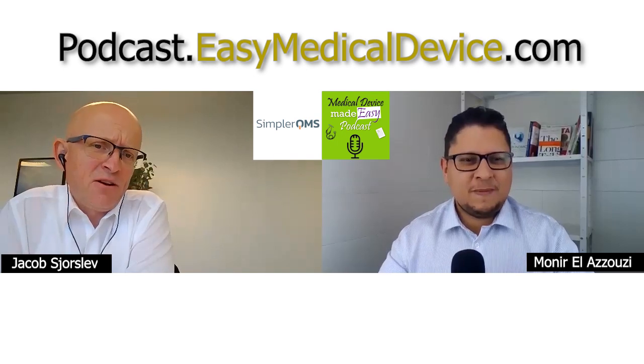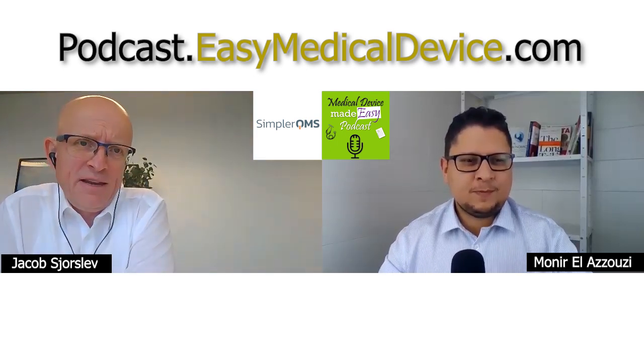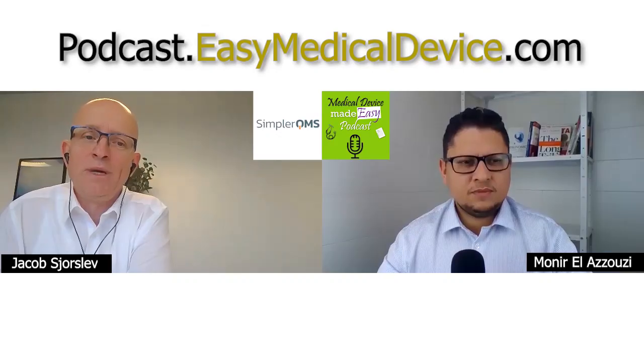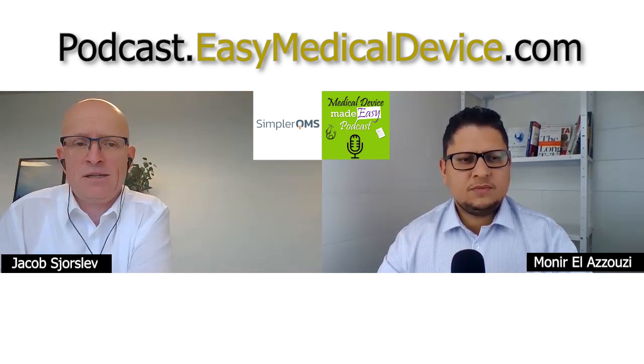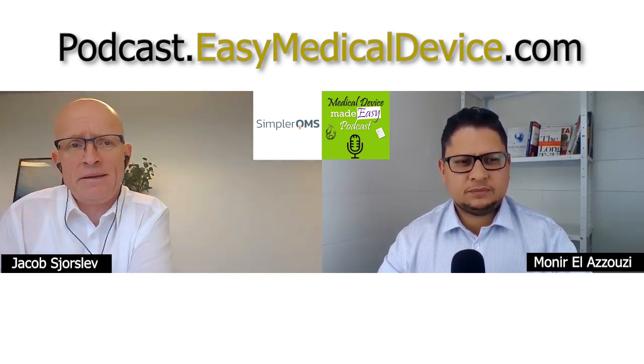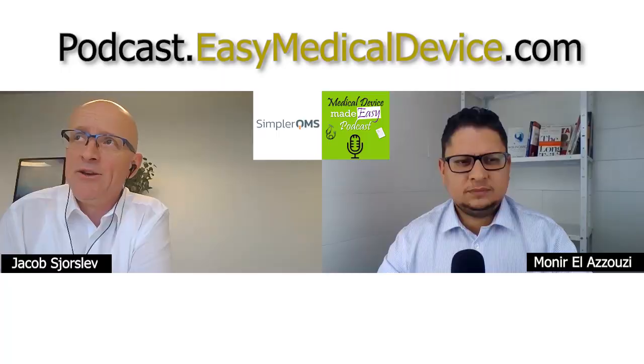And I think I should also make a point that if you have implemented a standard system in a standard way, that's easier to validate, instead of if you started with a standard system and then you did a lot of custom coding. All those custom codings, you have to validate individually and prove that it works. And you almost have to have a design control procedure around it, since you are going into the development of software actually. Okay.